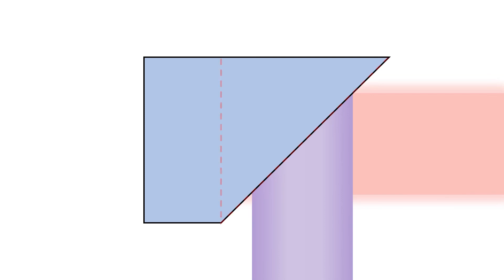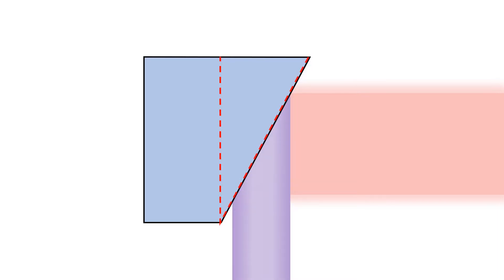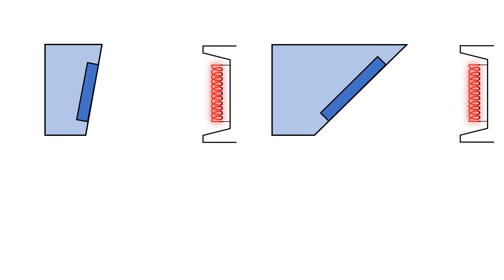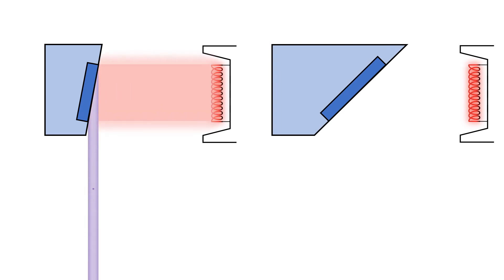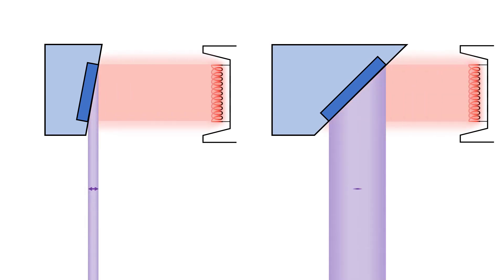How else can we change the effective focal spot other than changing the size of the incident electron beam? This is where the line focus principle comes in. By altering the angle of the anode, we can alter the size of the effective focal spot. Let's see what happens when we go from a 45 degree angle to something like a 20 degree angle. On the left is an x-ray tube using a small anode angle and on the right is an x-ray tube using a large anode angle. Notice how the width of the effective focal spot changes when using a small anode angle versus the large anode angle.